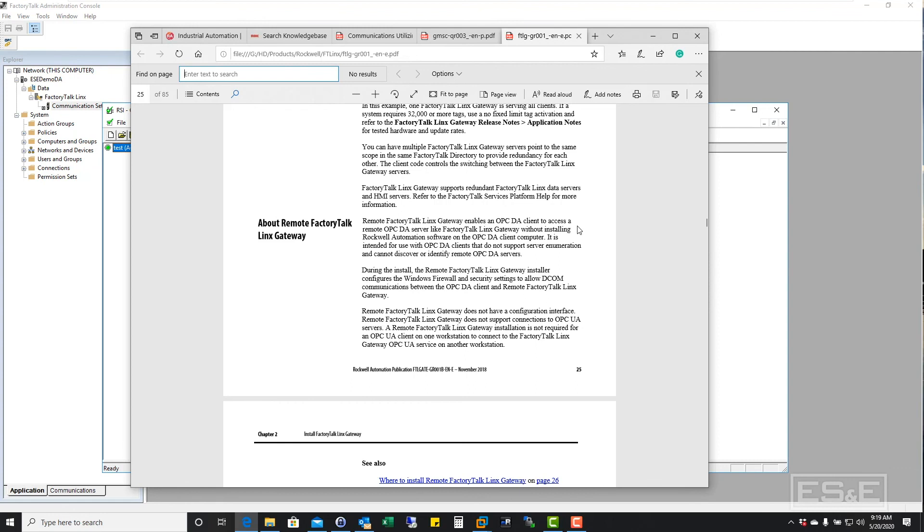And during the install, the remote FactoryTalk Linx Gateway installer configures the Windows firewall and security settings to allow DCOM communications between the OPC DA client and the remote FactoryTalk Linx Gateway.